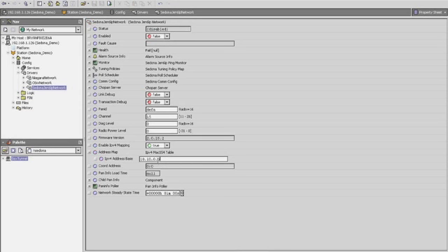So we're going to start with a 10.10.0.0 IPv4, and this is what is going to map the IPv6 address from the wireless Sedona controllers to the framework. Next is your channel. As you can see, channels 11 through 26 are available. There are 3 channels that operate outside of a standard 2.4 GHz 802.11 b/g/n network, and that's 15, 25, and 26. So in this case, we're going to use channel 26.